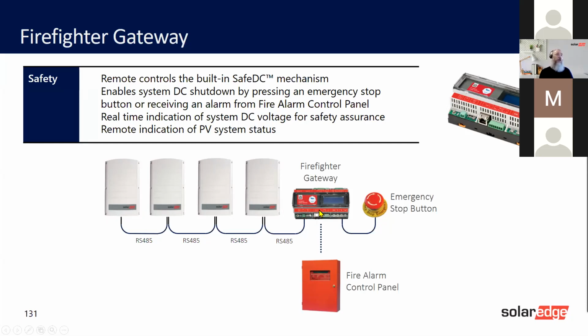This will then get the information, the contact will turn off or open or close, and then send the message again to the gateway. It will communicate to the inverters, and all the inverters will shut down production and wait until this device is reset. So this is normally put in reception. You would then press the emergency stop or the fire alarm will go off and all the inverters will shut down.